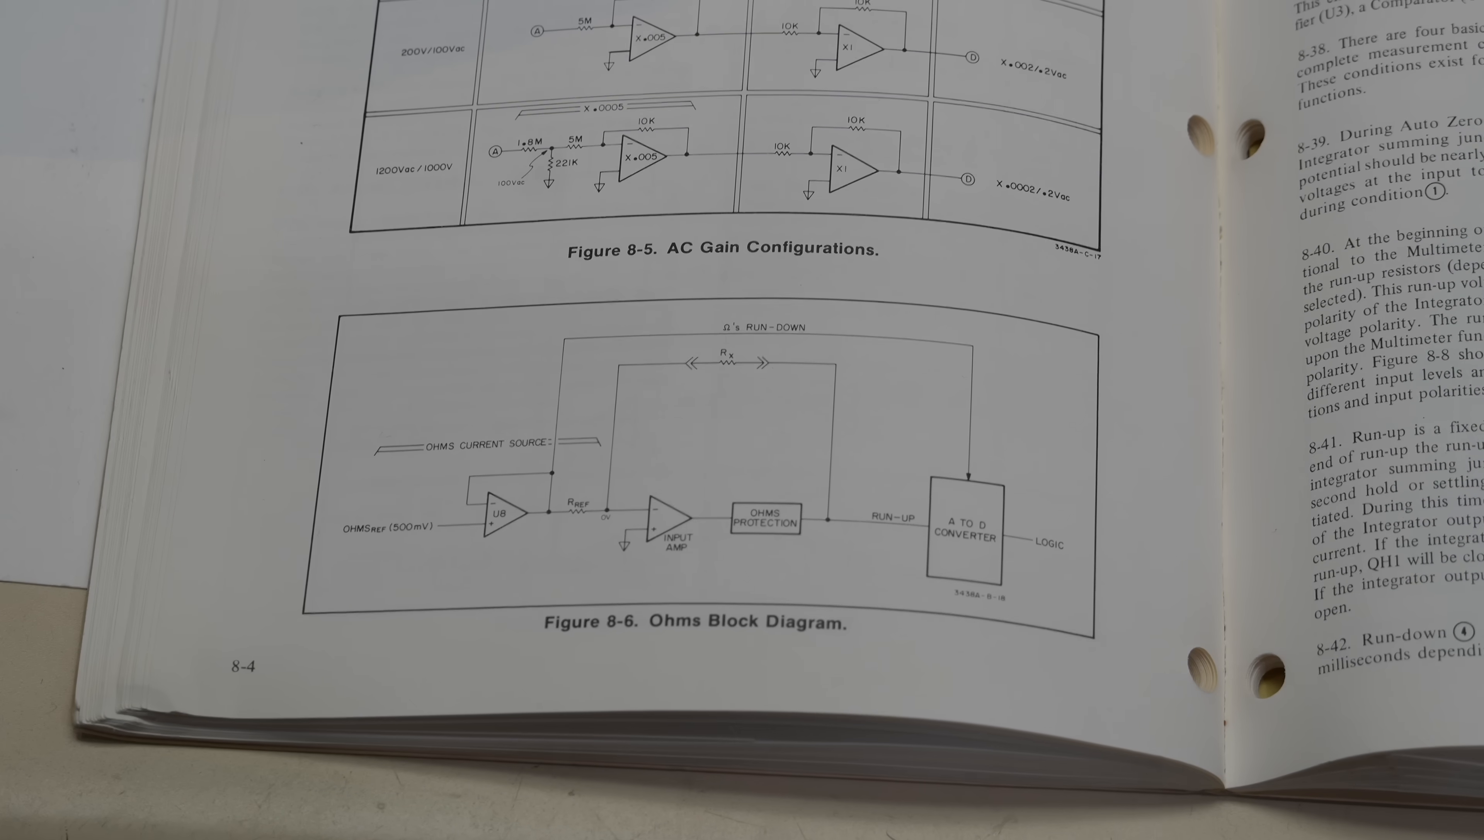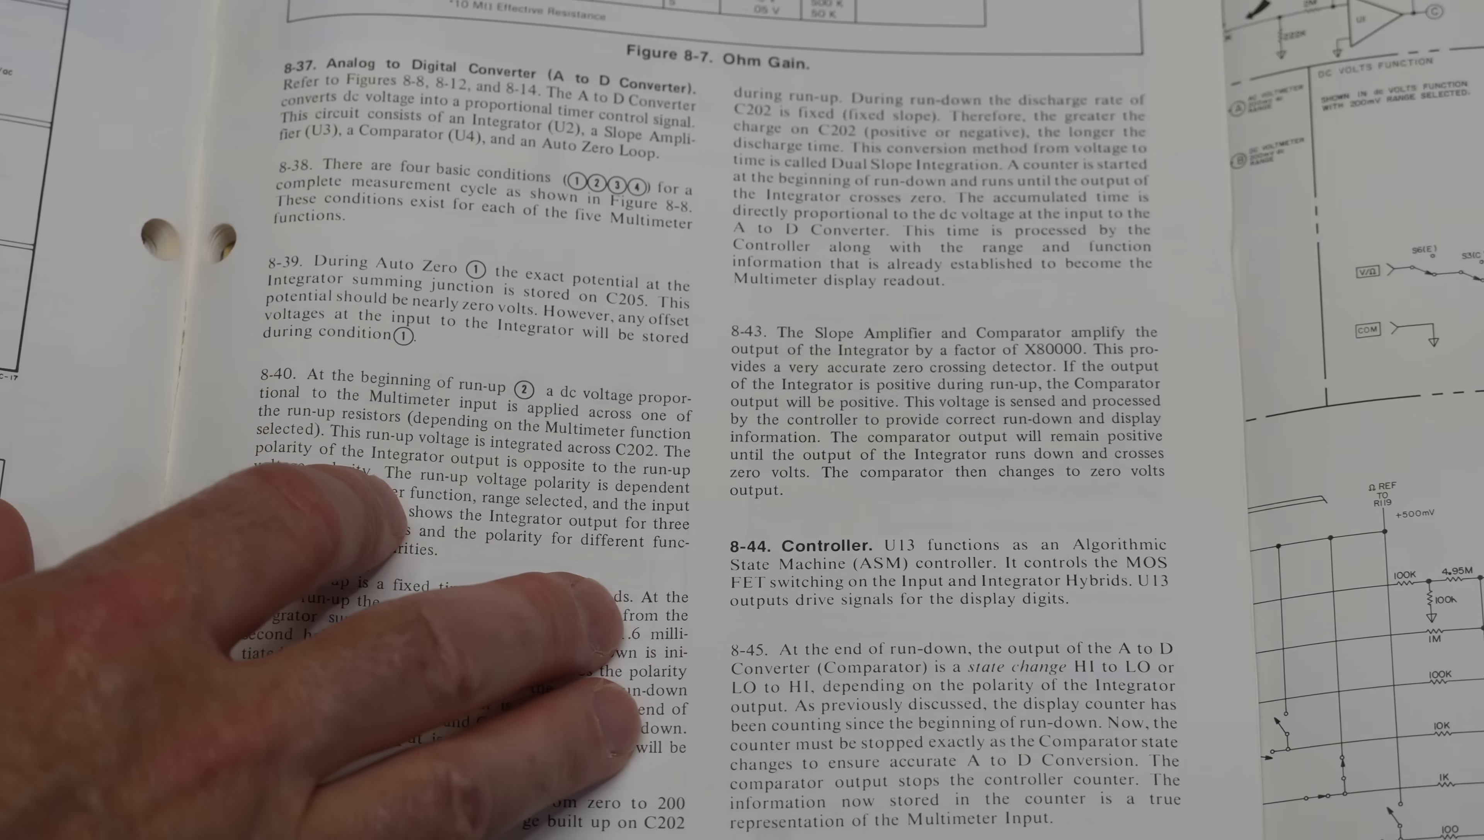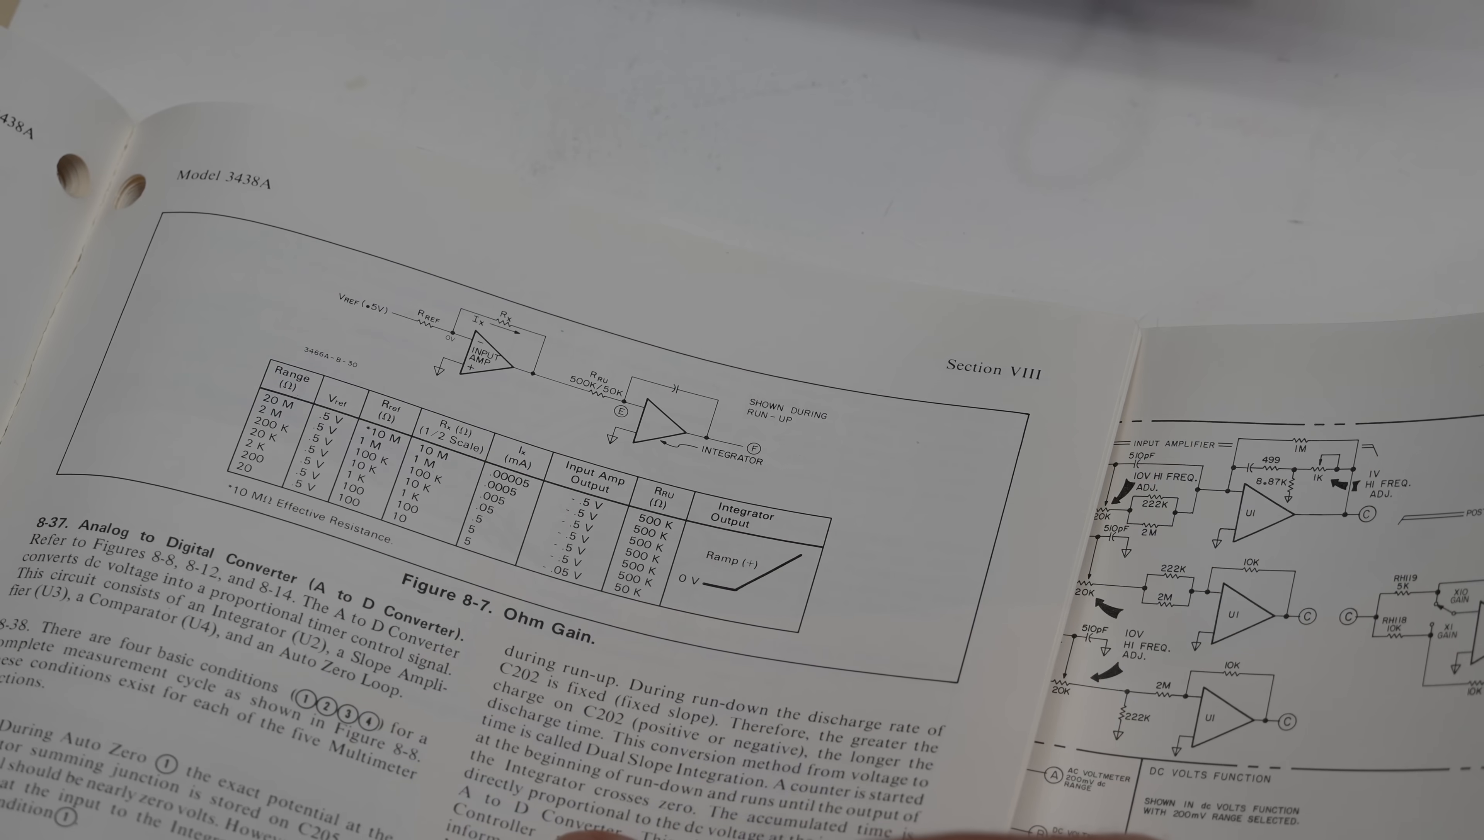So the way it does it is the current source actually doesn't put current through the test resistor, it puts current through a reference resistor. The reference is in the hybrid. And then the test resistor is put across an amplifier. And since it's an op amp, this point is always at 0V. So the op amp is going to nullify the current. If you look here, it's even more simplified. You have 0.5V across a reference resistor that's in the hybrid. And you put your test resistance across the input amplifier, and it will just balance it, depending on the resistor. It's a voltage divider, an assisted voltage divider really.